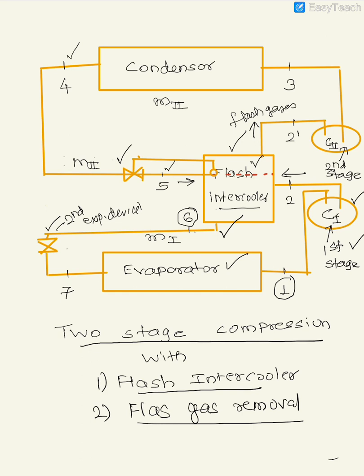The flash gases go into compressor 2. So what would be the mass balance? The mass exiting from the evaporator, we call it M1, goes to compressor 1. The mass M1 then goes to the flash intercooler. In the flash intercooler, because of the addition of flash gases from the throttling process as well as flash gases generated within the intercooler, you will have a higher mass M2.